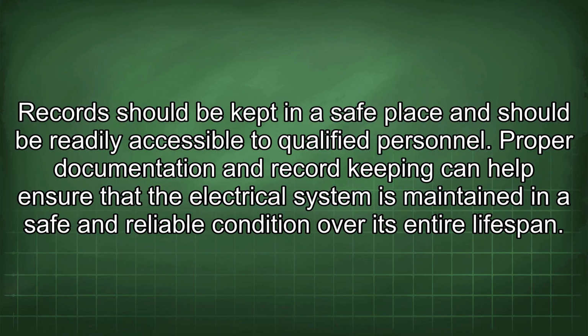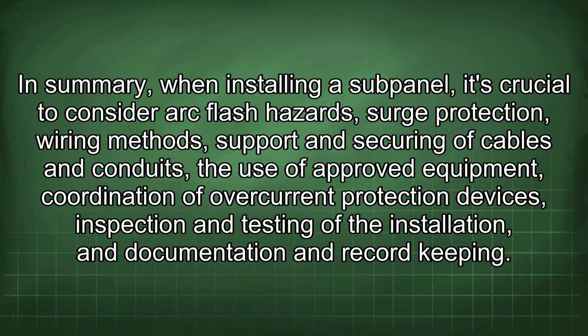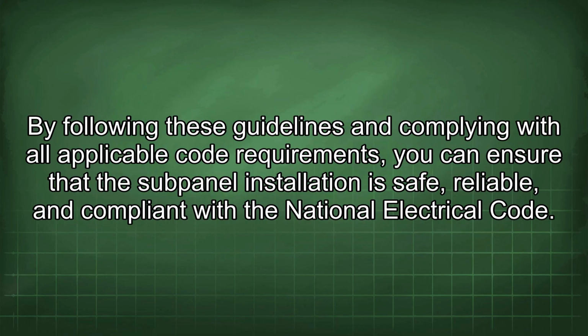In summary, when installing a subpanel, it's crucial to consider arc flash hazards, surge protection, wiring methods, support and securing of cables and conduits, the use of approved equipment, coordination of overcurrent protection devices, inspection and testing of the installation, and documentation and record keeping. By following these guidelines and complying with all applicable code requirements, you can ensure that the subpanel installation is safe, reliable, and compliant with the National Electrical Code.